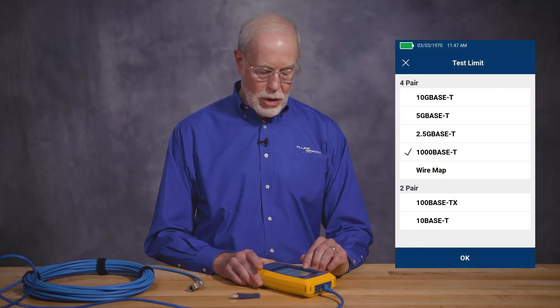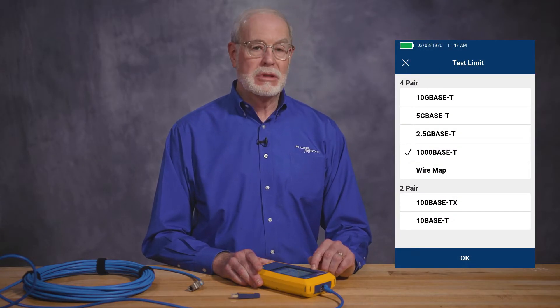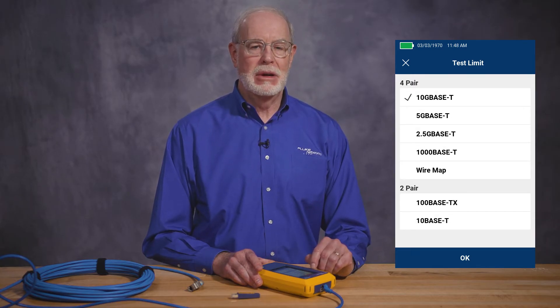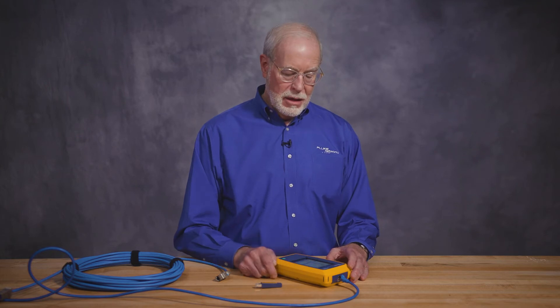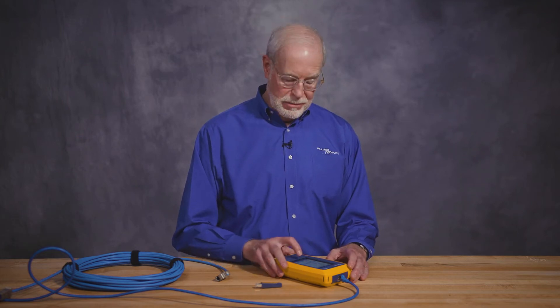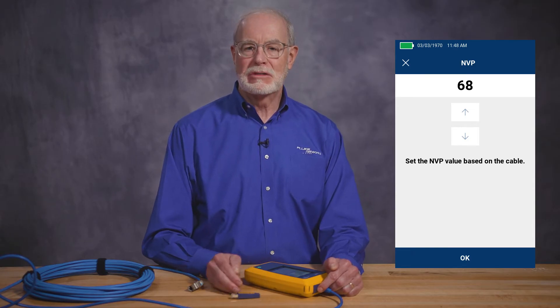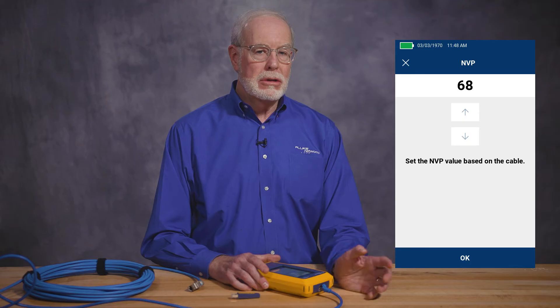Next are the cable settings. The test limit can be set anywhere between no test limit all the way up to 10 gig, and that determines the pass-fail limit of the tester. The tester can test a cable to 10 gig, but maybe sometimes you only need a cable that goes to 1 gig, so you might set the limit for a 1 gig cable. Next is the NVP, or nominal velocity of propagation. That determines how the cable tester makes its length measurements based on the amount of time it takes for a pulse to travel down the length of the cable. You can usually get that spec from the manufacturer of the cable.